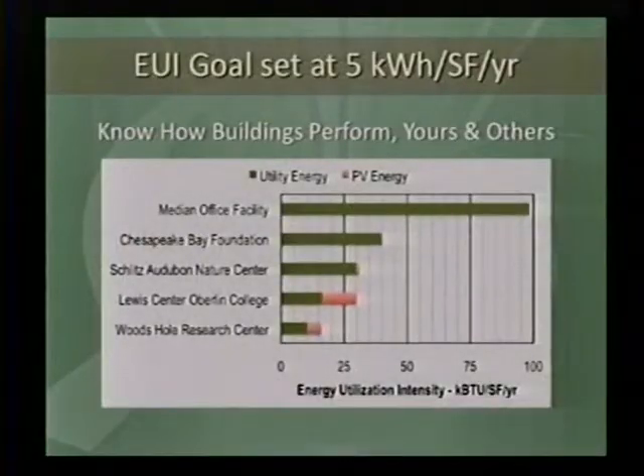Now, I believe that one of the most critical issues in establishing goals in building performance depends upon how well you know and understand how buildings perform, both yours and others. And part of our research included understanding a little bit about what other high-performance buildings were doing. This graph illustrates the energy utilization intensity in thousands of BTUs per square foot per year of a median office building from the 1960s all the way on up and earlier. So a great deal of energy use there, nearly 100,000 BTUs per square foot per year.